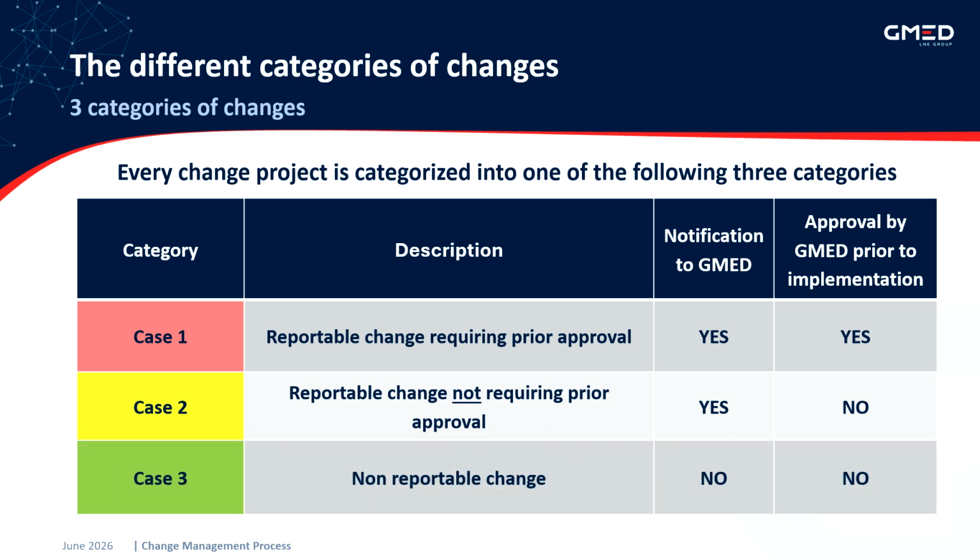Change projects categorized as Case 2 must also be reported to GMED, but do not require prior approval from GMED before the company can implement them. Finally, change projects categorized as Case 3 do not require notification to GMED.